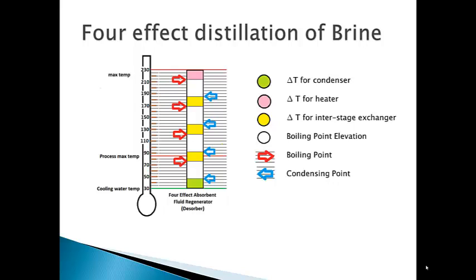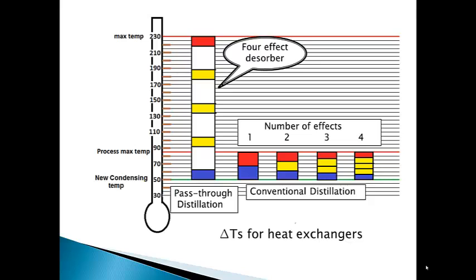Now suppose a great drought afflicted a particular area and authorities banned the use of evaporative cooling. All industrial facilities would then be forced to resort to direct air cooling using fin fans. This would raise the nominal temperature of the plant heat sink from 30 degrees C to 50 degrees. This slide compares the effect the change would have on different distillation arrangements. For the desorber of pass-through distillation plant, delta T's drop from 16 degrees to 12 degrees, a 25% impact.